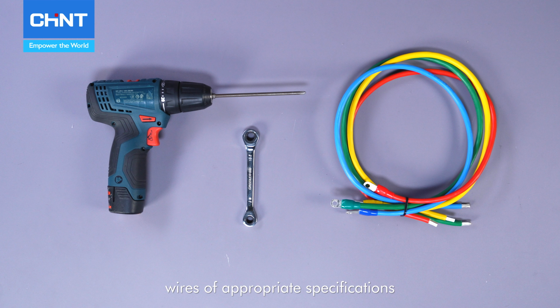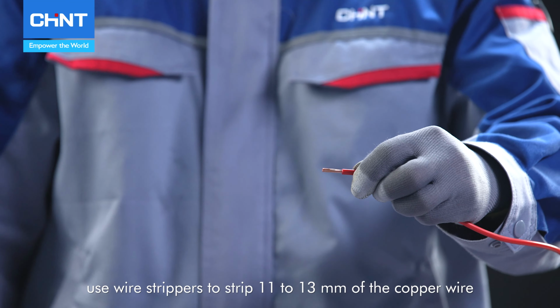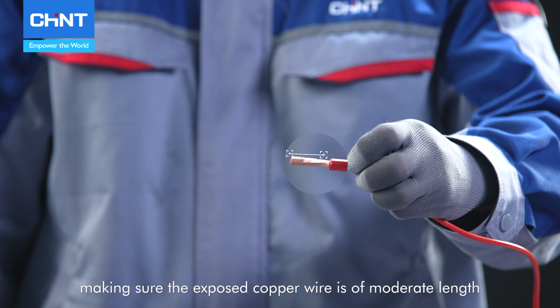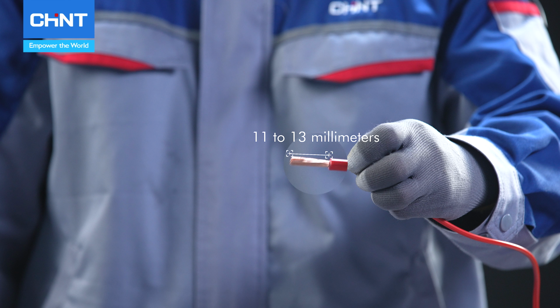Before starting the wiring procedure, open the back panel of the voltage regulator and find the wiring port. First, use wire strippers to strip 11 to 13 mm of the copper wire, making sure the exposed copper wire is of moderate length. Next, use wire crimping pliers to crimp the wire nose to the end of the copper wire to ensure the reliability of the connection.